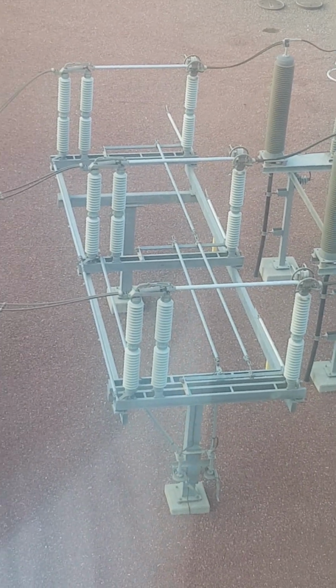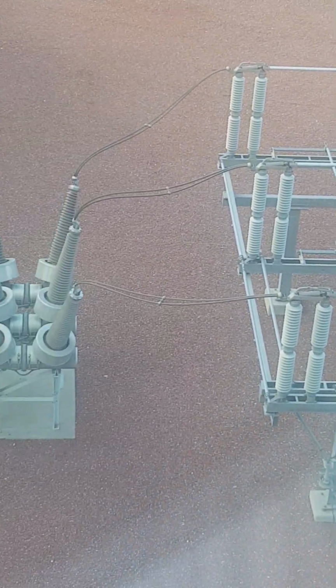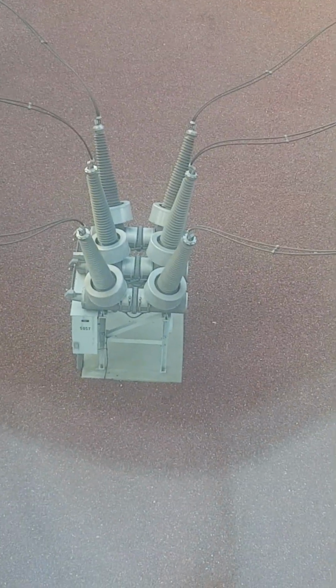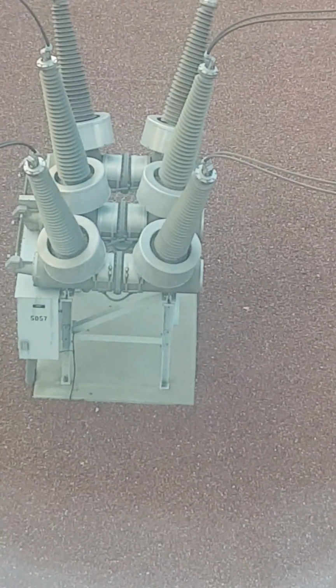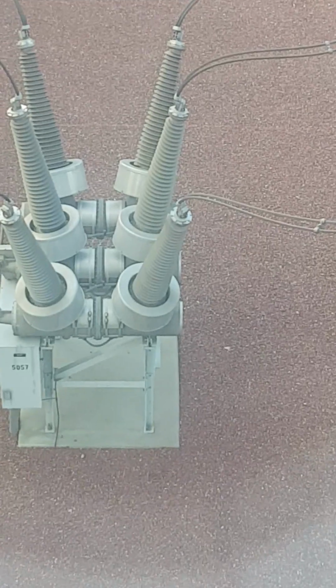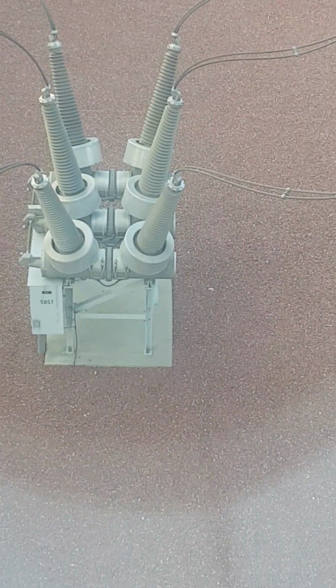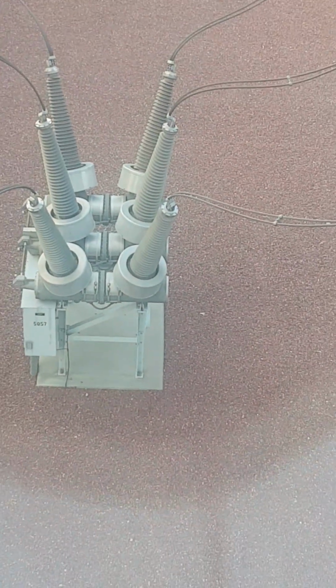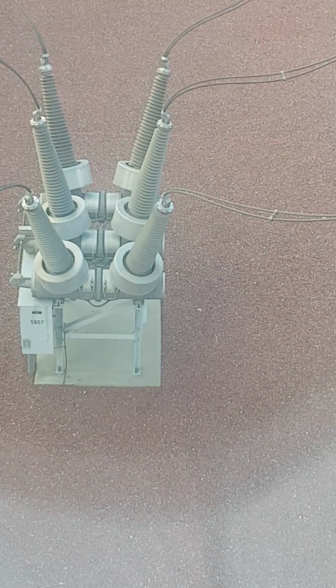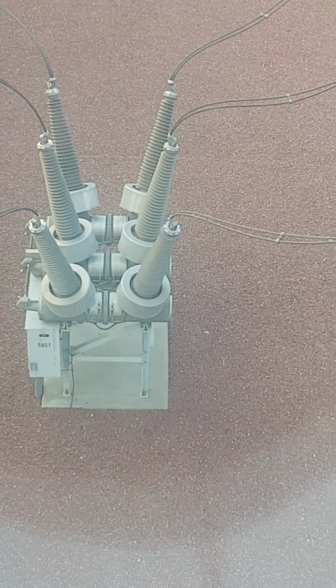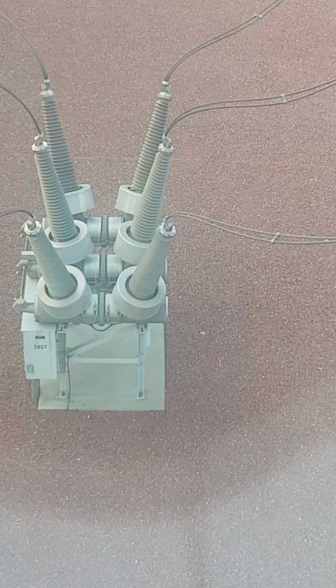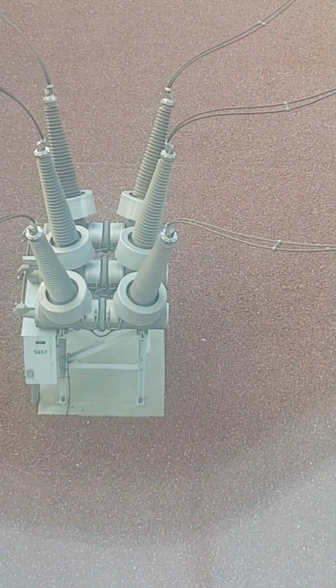How can we interrupt the fault current and the load current regularly? We have another device, which is the circuit breaker. Look here, this is the circuit breaker. And the circuit breaker here is an SF6 one. And if you look carefully here at the bottom of the bushing, you will see a donut shape. This is a current transformer. The objective of this current transformer is to sense the current, and if it exceeds a certain value, it will send a signal through the relay to the breaker to interrupt the circuit.